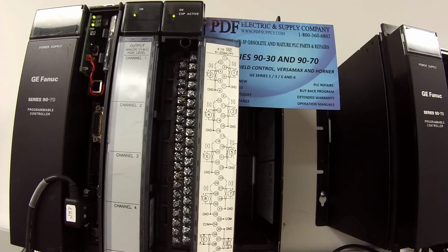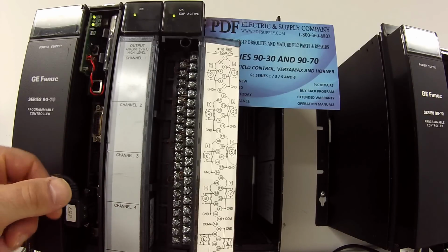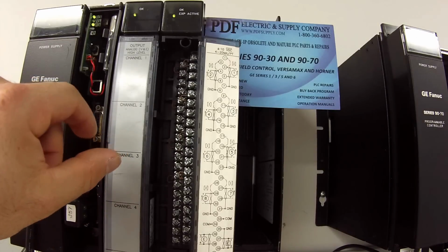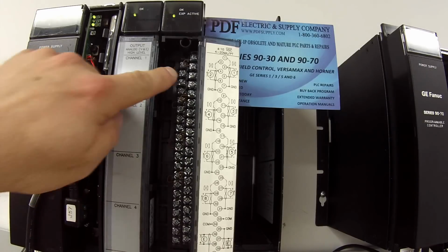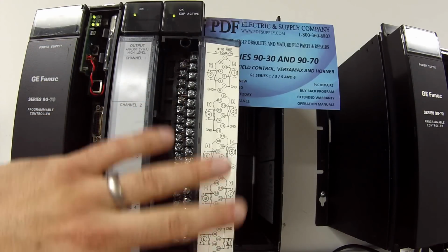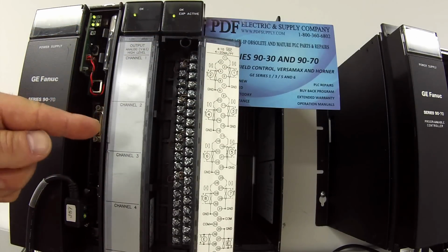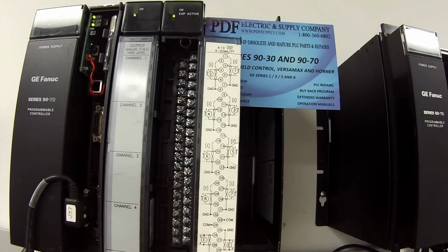So we have another power supply here that's adjustable from 0 to 48 volts. You don't obviously want to go that high, but you can kind of slowly turn up the voltage as it gets to 10 volts and test each channel thoroughly all the way through the whole spectrum of the voltages from 0 to 10 volt DC. And I do recommend that. If you think you're having a problem with the processor, you should definitely do that.